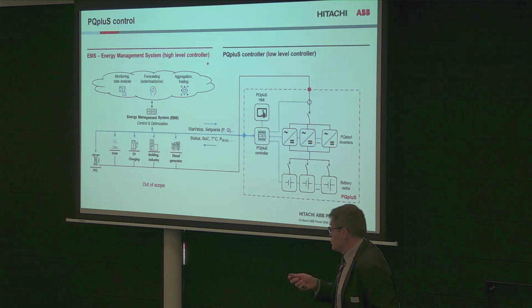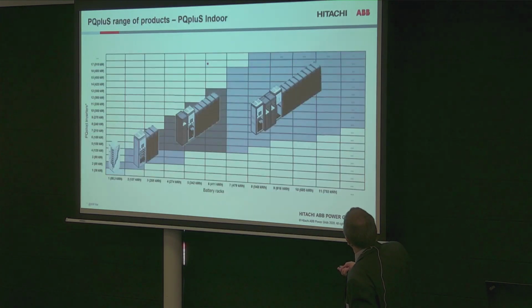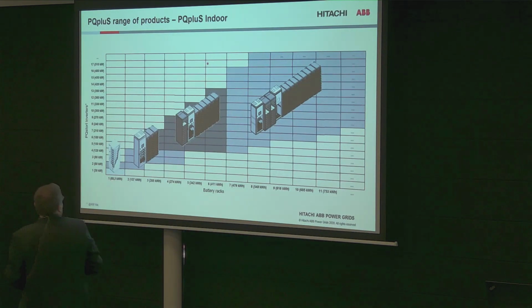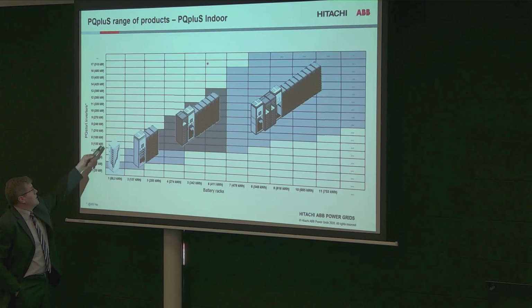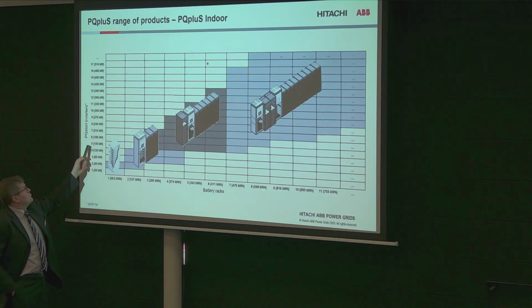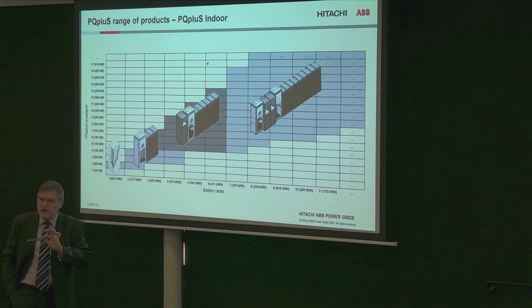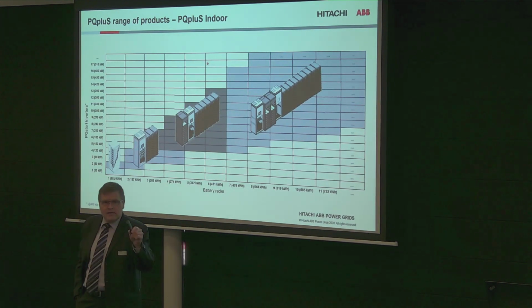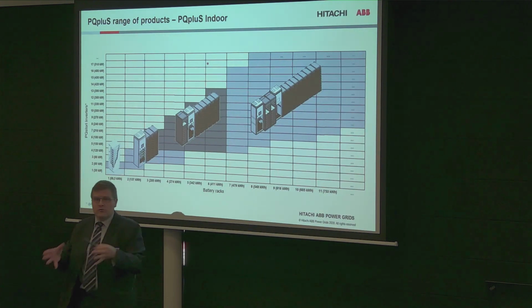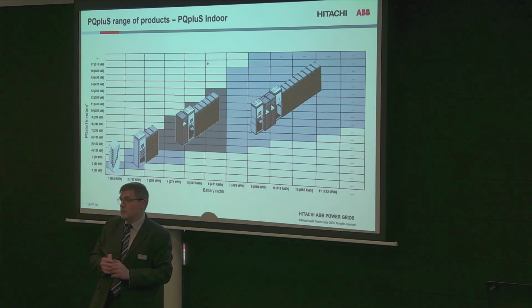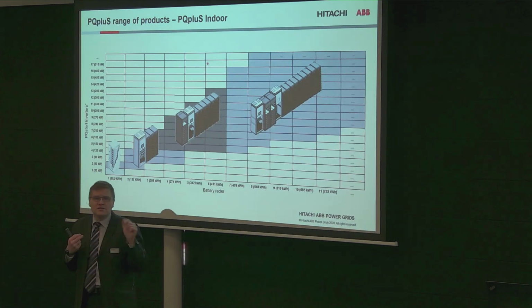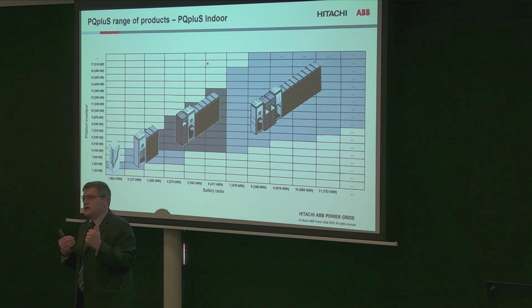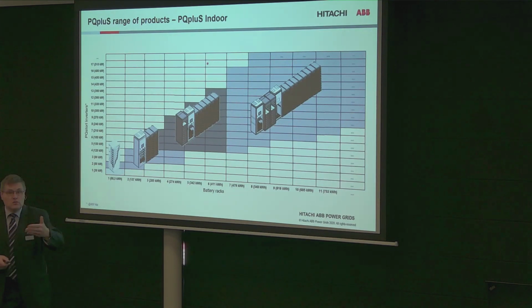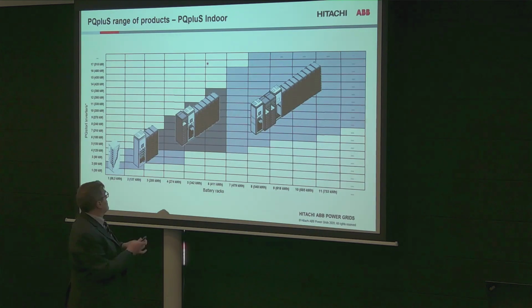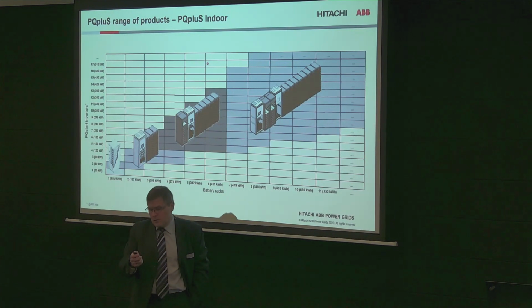Alors, what is a turnkey solution? So here it depends on the range of power you need. We can provide a cabinet from 30 kilowatt to 100-ish kilowatt. We have to mention, here we mention kilowatt, but actually it is kilowatt and kilowatt hour, because we have the power of the inverter for the charging of the battery and the value of the battery. So this is two values. We assume here C1, so that means that we have the same rating of the inverter as for the battery. So here 30 kilowatt, it's 30 kilowatt inverter and 30 kilowatt hour battery, so it's C1 charge. So we have different types of solution depending on the power we need.